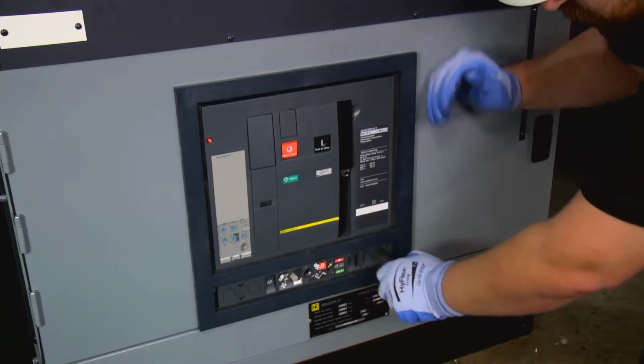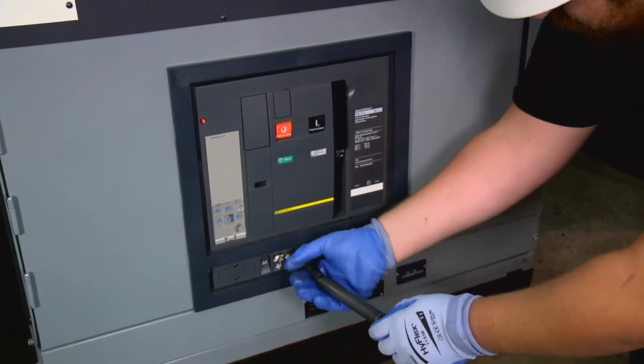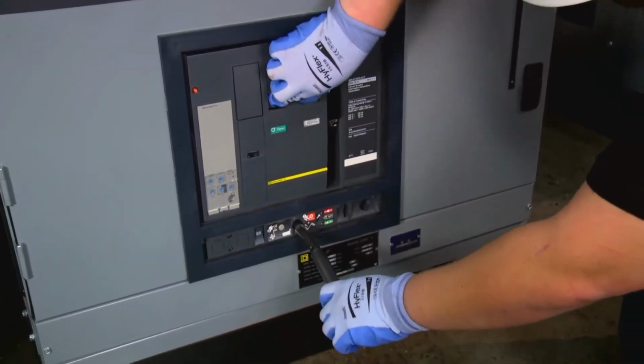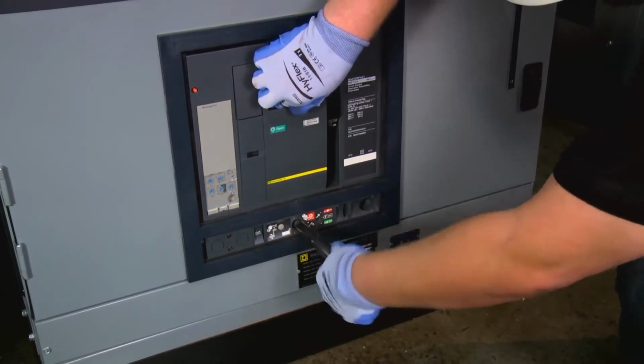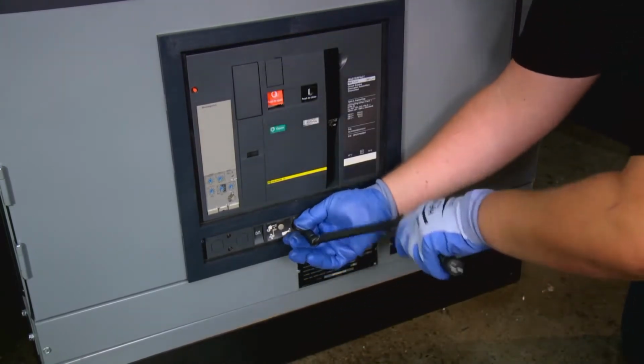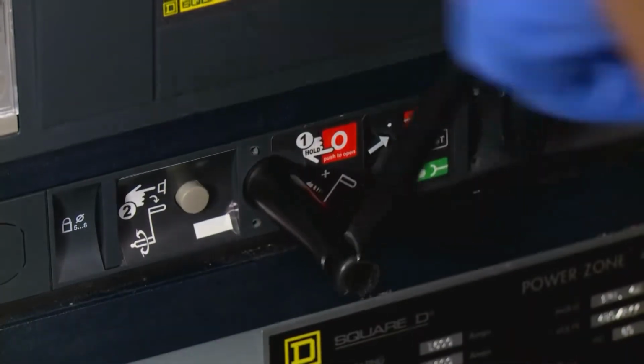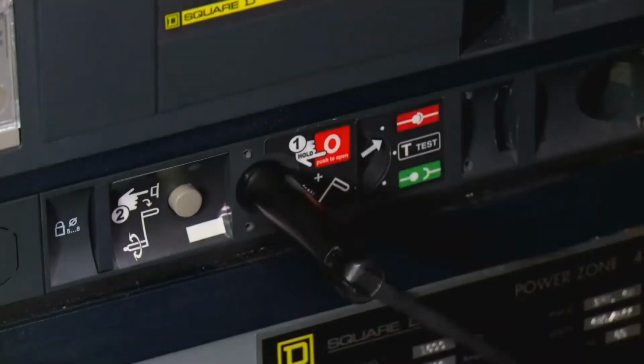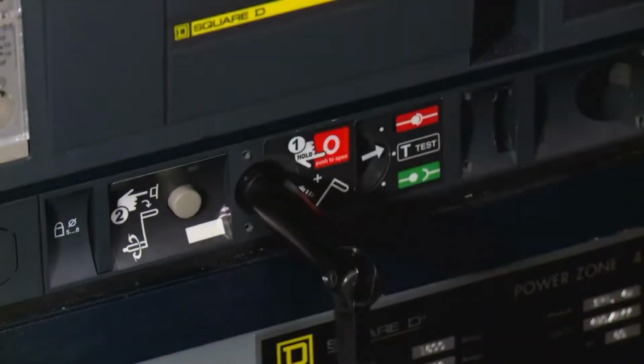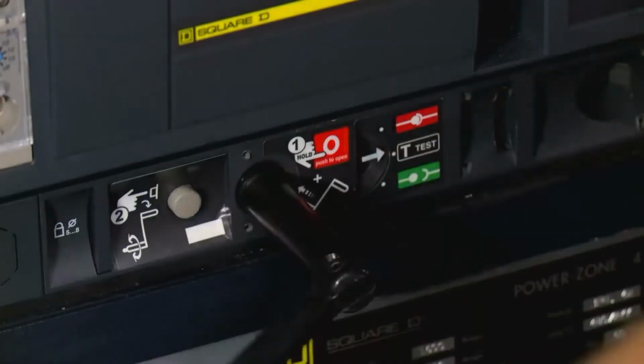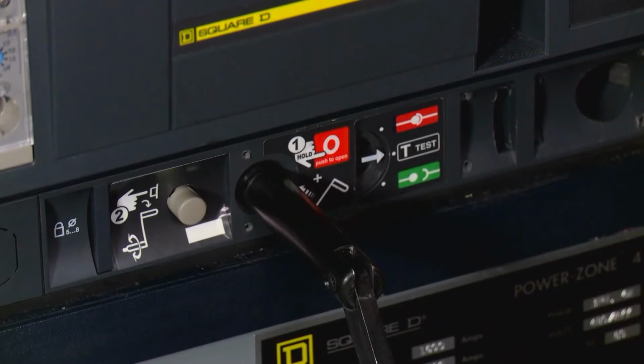To do this, remove the racking handle from the front right side of the cradle. Fit it into the racking mechanism slot and turn the handle counterclockwise. The arrow on the front of the cradle will move toward the test position on the display. When you hear a click, you've reached the position.